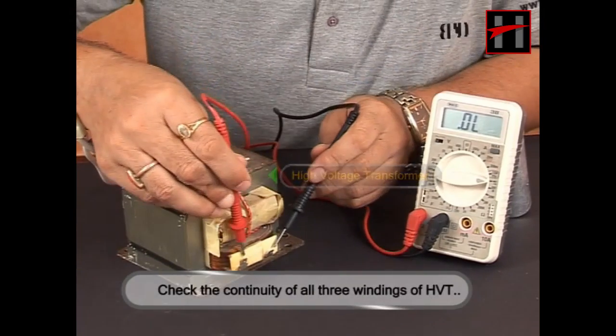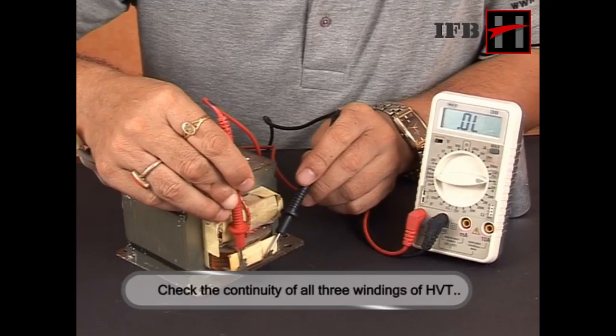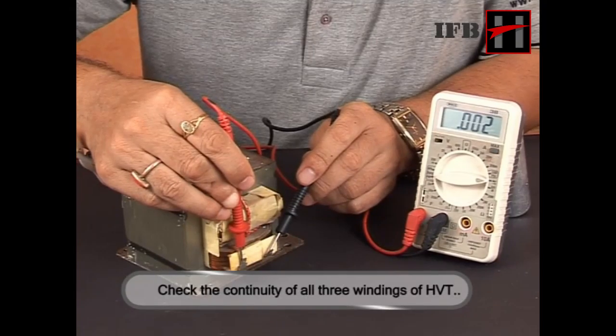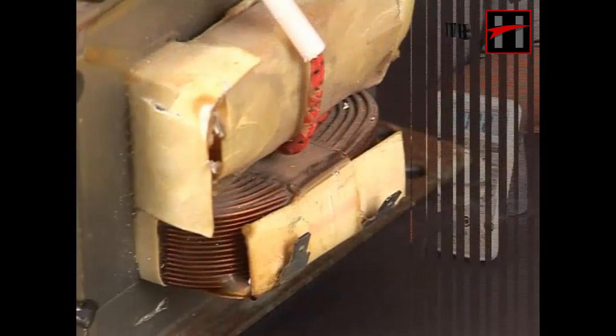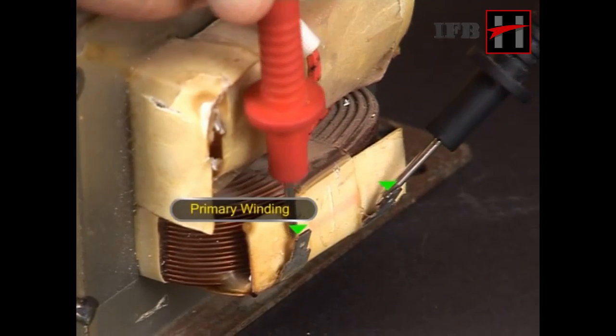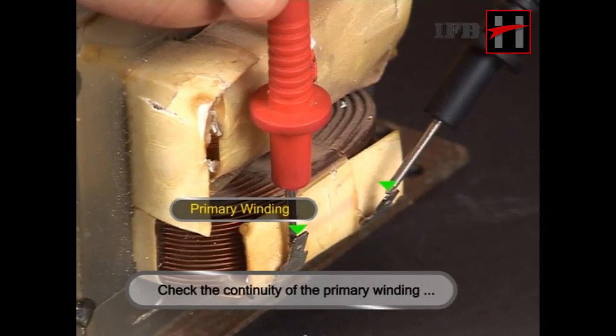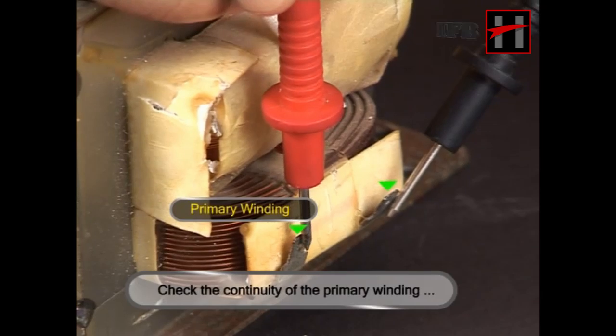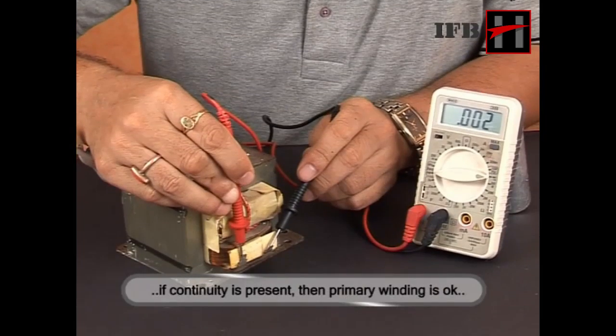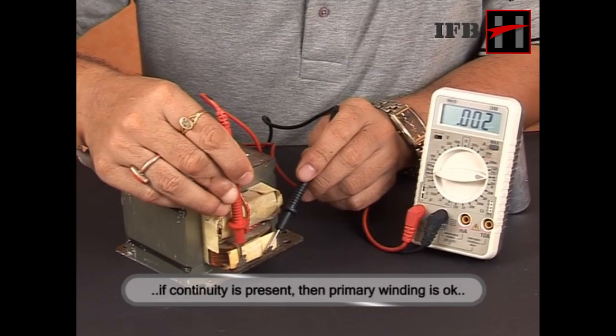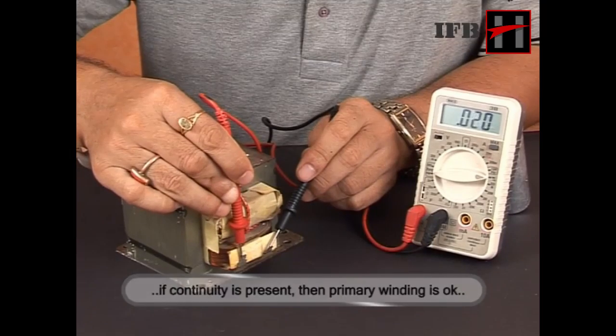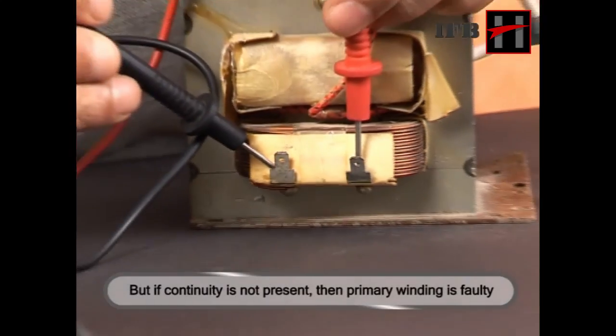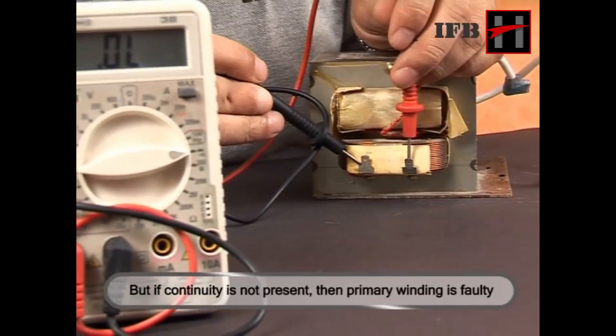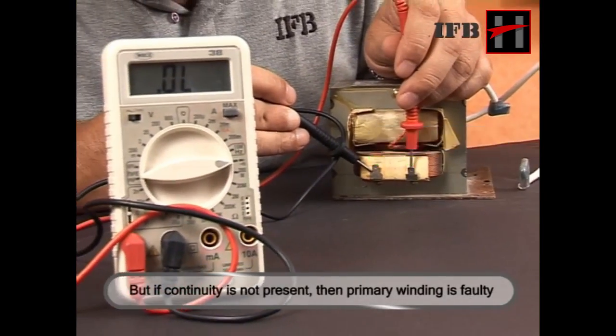Check the continuity on all the three windings of the high voltage transformer or the HVT. First, check the continuity on the primary winding. If continuity is present, then the primary winding is okay. But if continuity is not present, then the primary winding is faulty.